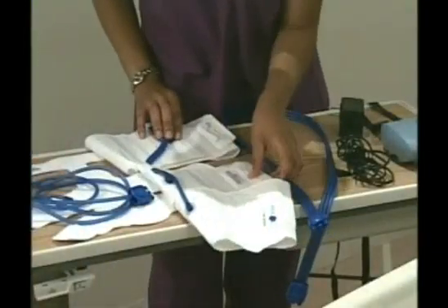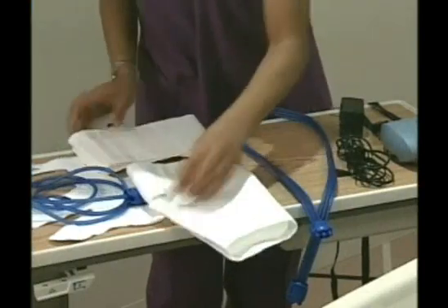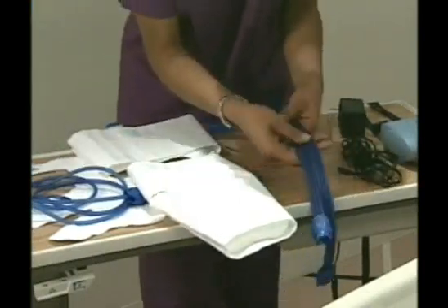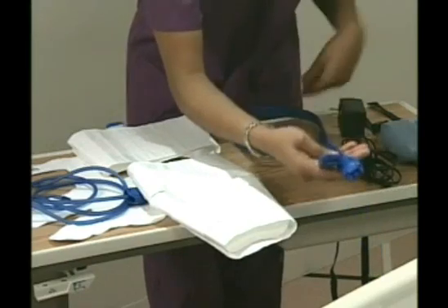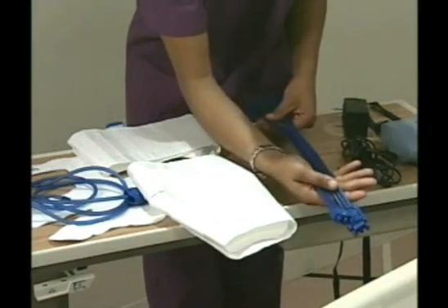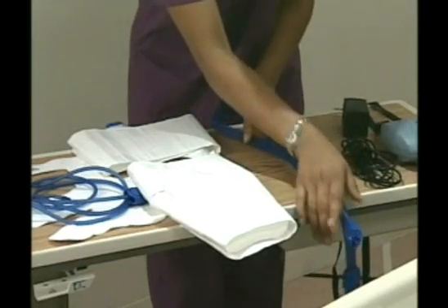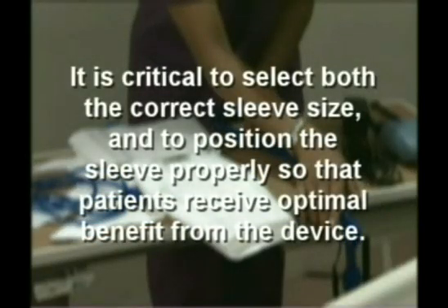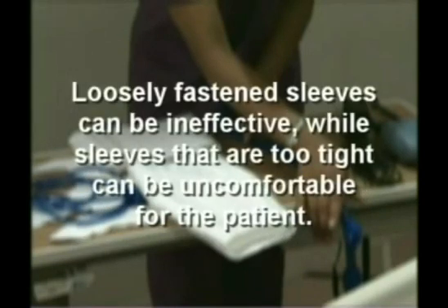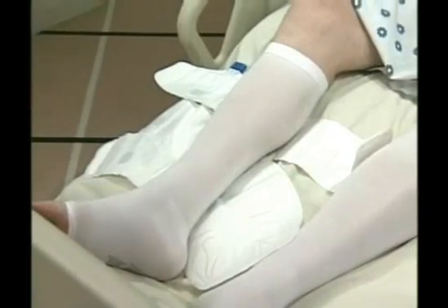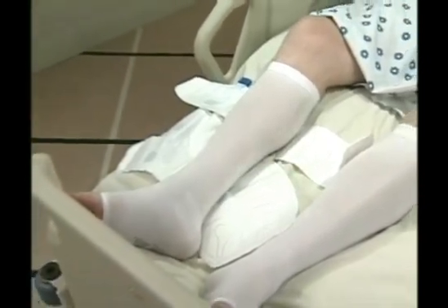Examine the sleeve and reusable connecting tubing to make sure that they are not cracked or damaged in any way. This product demonstration uses the short extension tubes. Longer tubing is available for operating room use. It is critical both to select the correct sleeve size and to position the sleeve properly so that patients receive optimal benefit from the device. Loosely fastened sleeves can be ineffective, while sleeves that are too tight can be uncomfortable for the patient. We recommend positioning the sleeves over cotton stockings to enhance patient comfort.